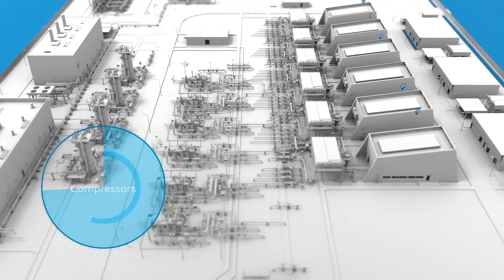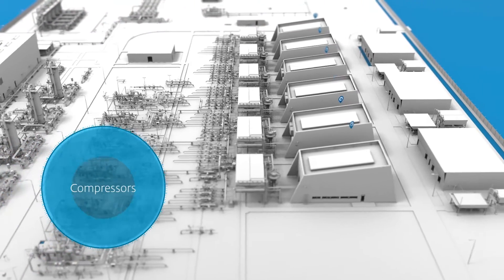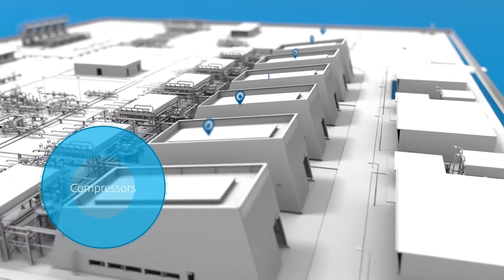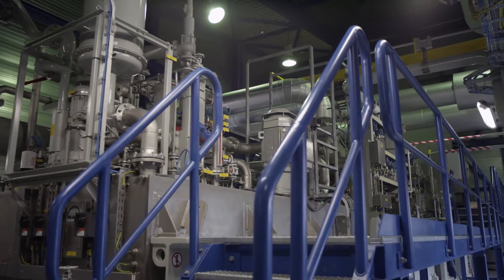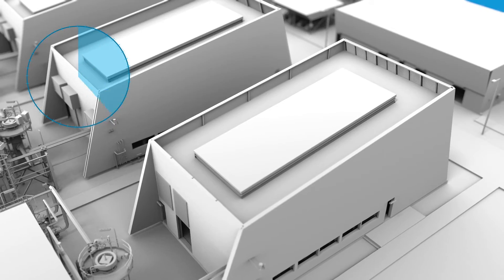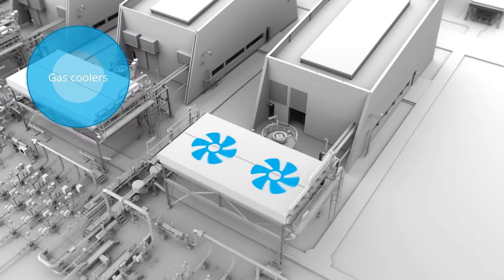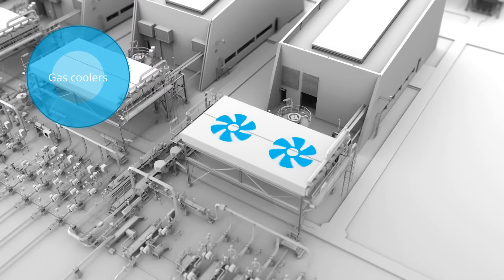When gas is injected into the cavern, it is compressed to between a minimum of 80 bar and a maximum of 180 bar. This is done using electrically operated compressors. The increase in pressure heats the gas to around 100 degrees centigrade, so it needs to be cooled before injection.